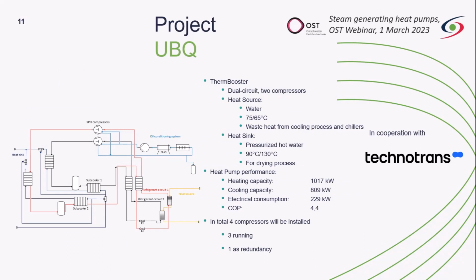Here you see the PID of these units. So we have two of these units. You can see here the two compressors, and so they are working more or less completely independent from each other. And as I said, we are delivering two units. Each of these units can deliver approximately 1 megawatt. So means in total we install 2 megawatts of capacity.